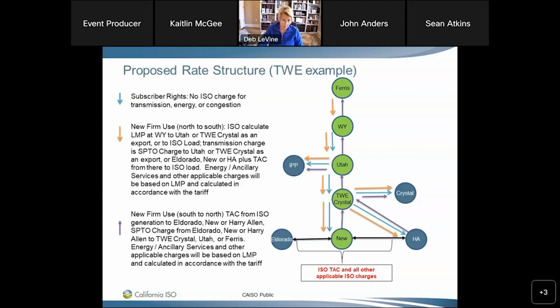So the thought at the moment is that the teal lines are the subscribers. The generation is connecting at Wyoming substation, then it goes down to Utah. Between Wyoming and Utah is a 3,000 megawatt DC line, and 1,500 megawatts will get off, or have the capability of getting off, at IPP. That's an AC line, and the remaining 1,500 megawatts will come down to TWE Crystal, which could connect with Crystal, could connect with Harry Allen, or connect with what we're calling the new substation, which would be a looped-in substation between the Harry Allen-El Dorado line that's already part of the ISO control grid.